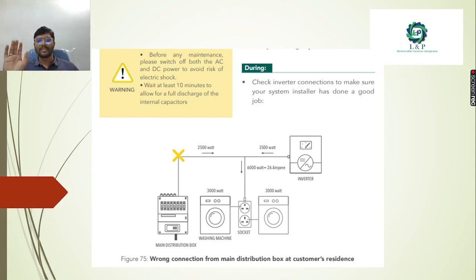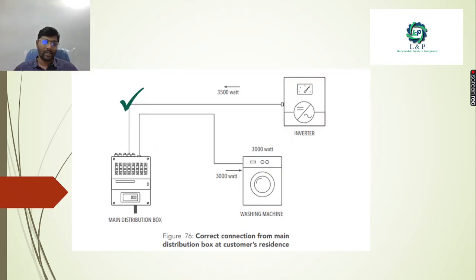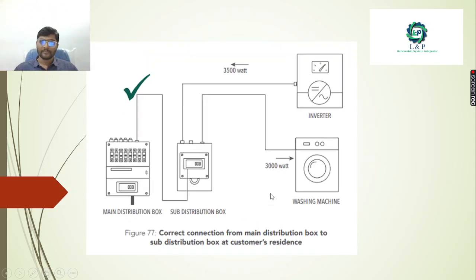Now, during the inverter checking, you need to ensure whether the system installer has done a good job or not, because the energy production from the inverter should go to the main distribution box. From there only it should distribute to the other loaded equipment. If you connect directly, so that only 2500 watts is going to the main distribution board and the rest you are connecting directly to the loads, then it is a wrong connection. This is the correct connection. The energy generated from the inverter should go to the main distribution board. From the main distribution you can distribute to the loads.